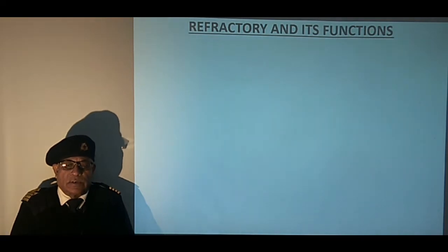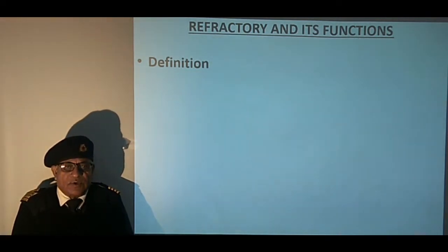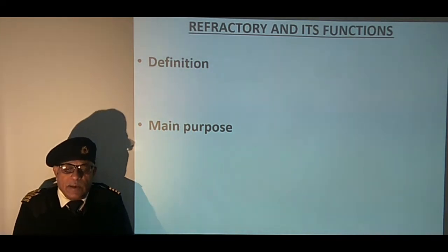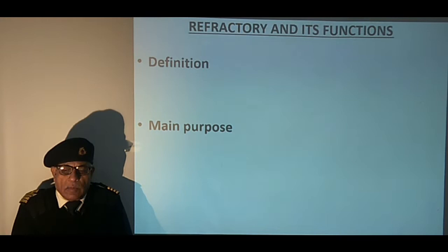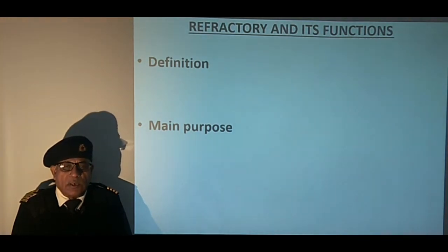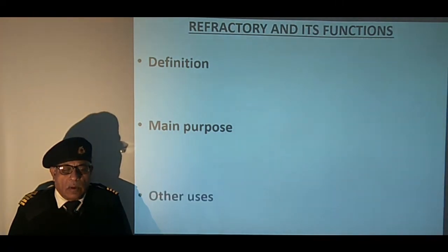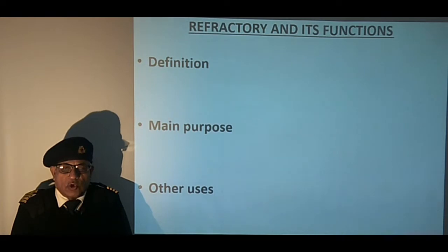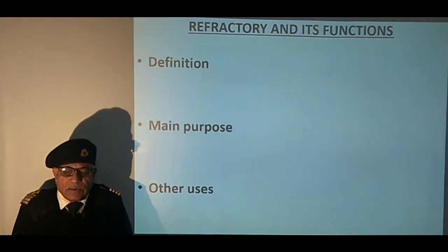Refractory is defined as an insulating material which can withstand the furnace temperature, usually up to 1650 degree Celsius, while retaining its shape without deformation. Refractory is mainly used in the furnace of water tube boilers around the water walls, although it is also used in the tank type smoke tube boilers where the furnace is not surrounded by water and in the inspection covers for the smoke tubes. It protects the boiler casing from overheating and distortion, thereby preventing the leakage of gases into the machinery space.